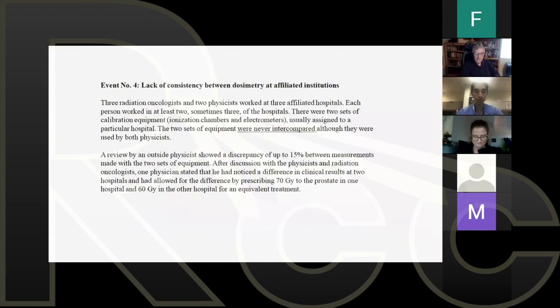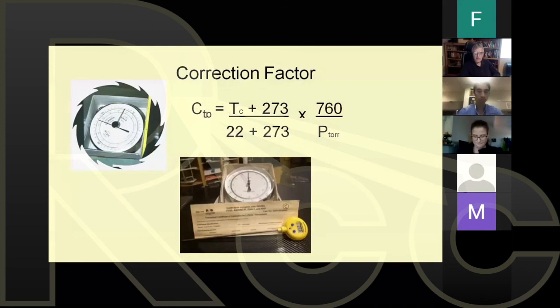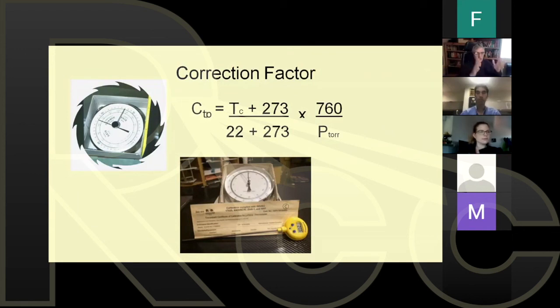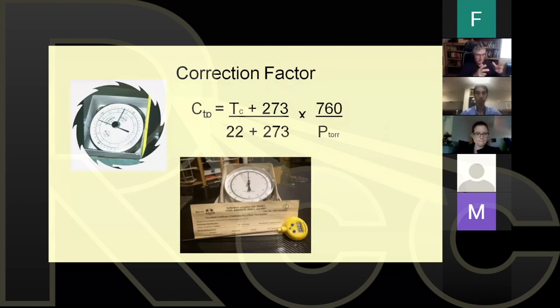You have to correct your chamber reading with temperature and pressure correction. The electrometer itself, you want to make sure that the electrometer has been calibrated and that you're using it on the correct scale, usually 10 to the minus 8 or 10 to the minus 9 coulombs. The chamber geometry is so important. Are you measuring in water, and are you measuring with the correct field size, the correct distance, and the correct depth? So those are all important setup parameters that you need to use.